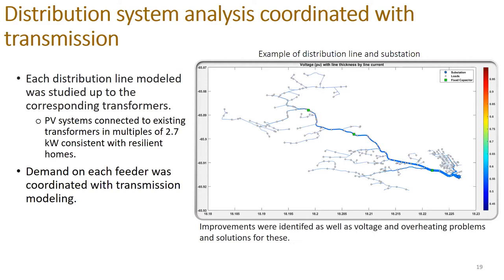We surmised, or made the assumption, that where there were single-phase distribution transformers, there would probably be residential homes. So we located the residential PV and battery systems at the locations where there were single-phase distribution transformers. And we scaled them, or allocated them, based on the size of those distribution transformers. That is, if there's a large transformer, that is representative in all likelihood of multiple homes or a large apartment complex or something along those lines. Where there were three-phase distribution transformers, we made the assumption that that would likely be a commercial facility.